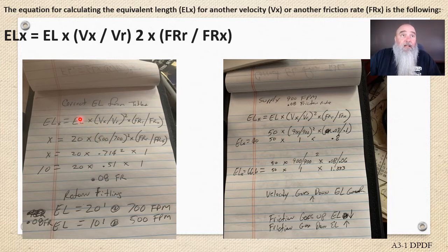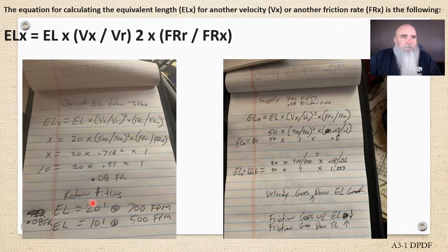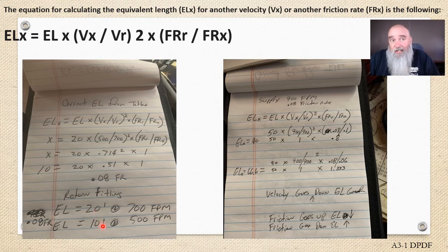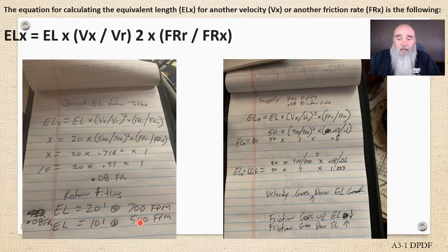This is me doing the math, and this example right here I had the effective length of a fitting at 700 feet per minute dropped to—this fitting, 20, was cut in half just by dropping my velocity to 500 feet per minute.